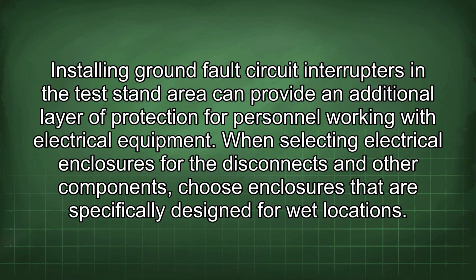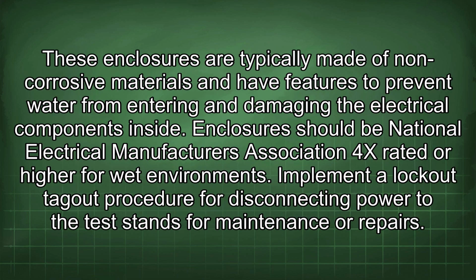When selecting electrical enclosures for the disconnects and other components, choose enclosures that are specifically designed for wet locations. These enclosures are typically made of non-corrosive materials and have features to prevent water from entering and damaging the electrical components inside. Enclosures should be National Electrical Manufacturers Association 4X rated or higher for wet environments.